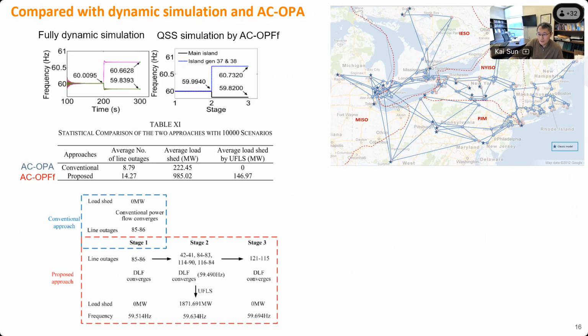Here is a more detailed comparison of one scenario. If you run only the power flow without frequency, it takes just one stage to finish. It seems to be just a single contingency. But if you run this frequency-dependent power flow model, it will tell you there are 3 stages. One failure will cause maybe a frequency event, like the frequency dropping to a certain level, so you need to do some load shedding, and the failures can propagate through more stages.